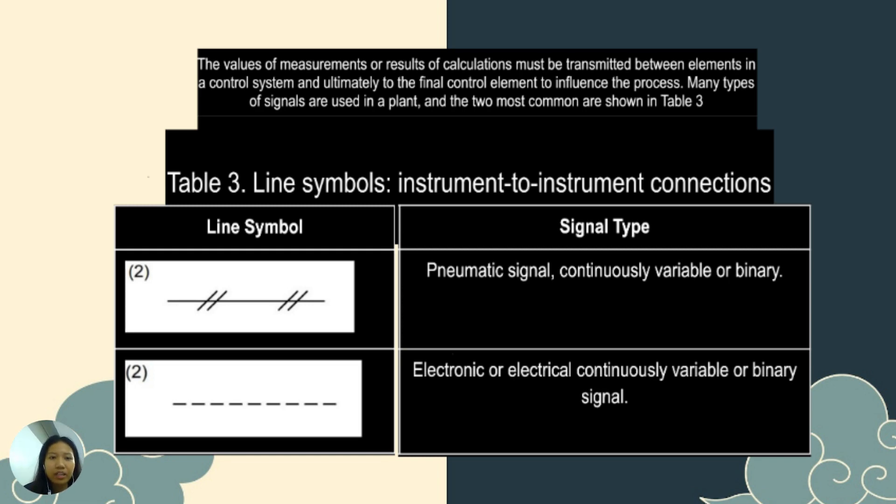For the third topic, the line symbols instrument to instrument connections. The first picture for the line symbol is for the pneumatic signal continuously variable or binary. And for the second picture, it is the line symbol for the electronic or electrical continuously variable or binary signal.